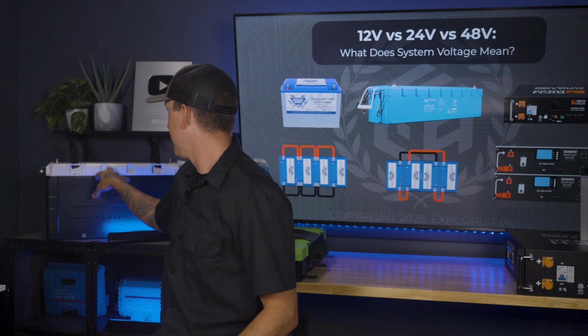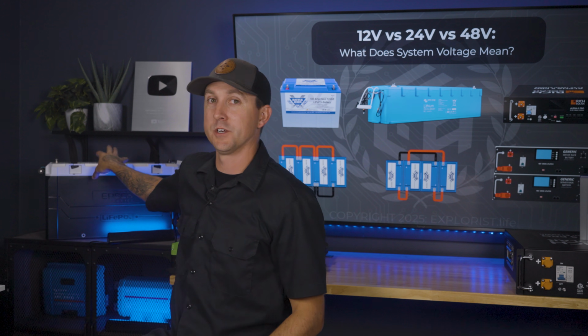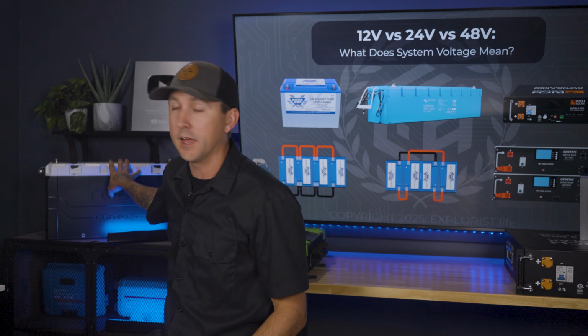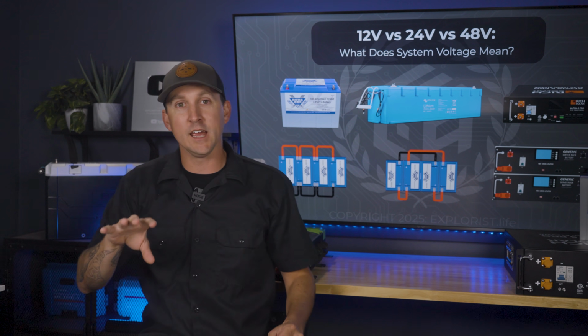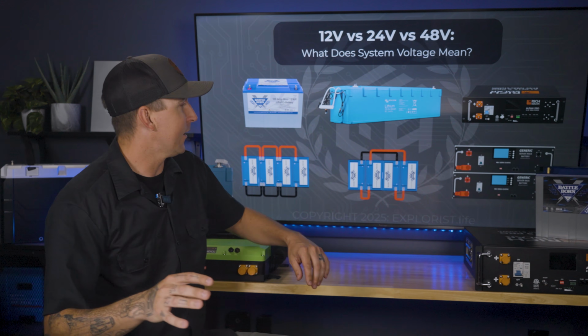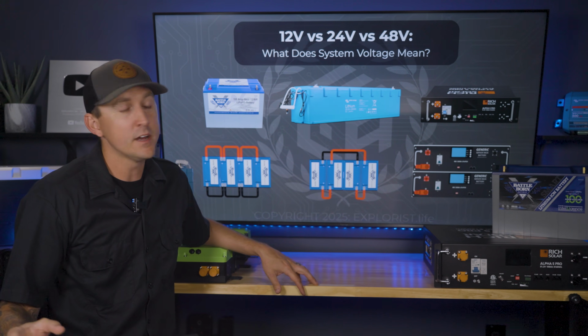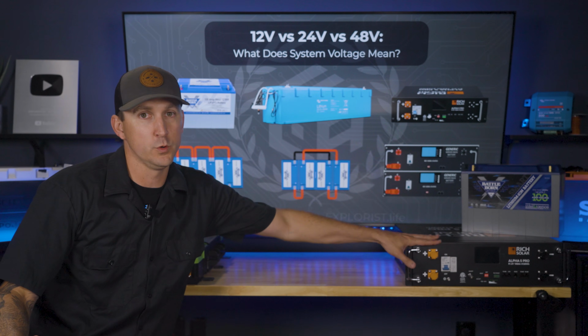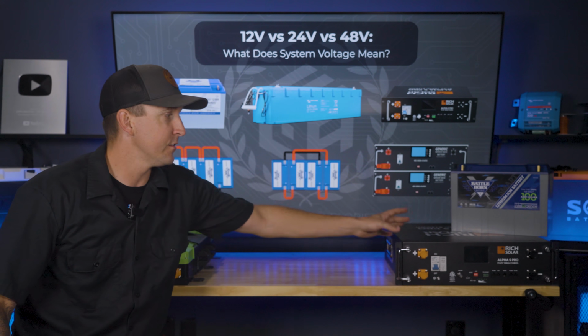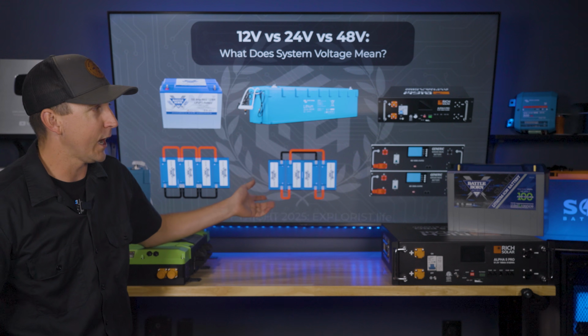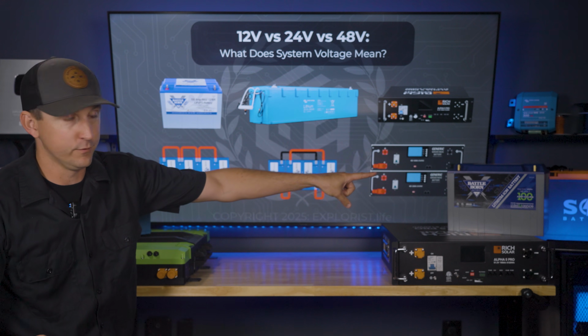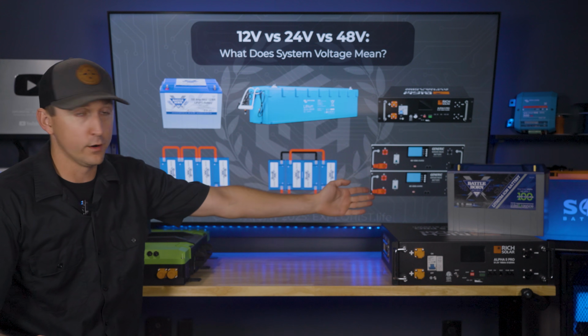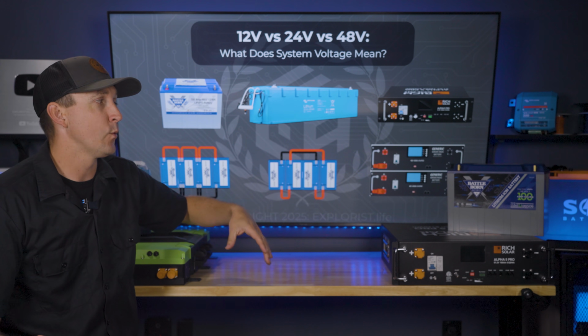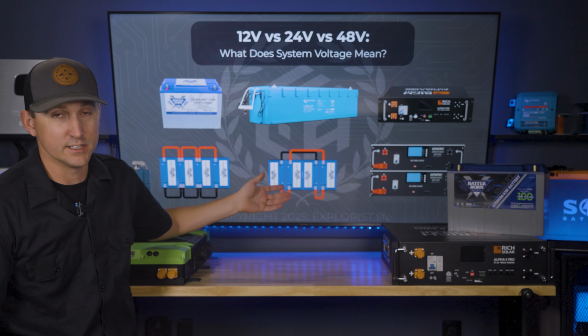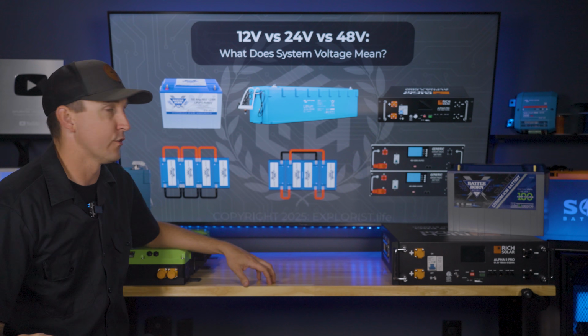Now this exact same battery size and footprint comes in a 12 volt, 24 volt, and 48 volt version. But understand that whenever I'm talking about battery system voltages, I'm not talking about the actual individual battery voltage, because you could have a 48 volt battery bank made up of 12 volt batteries. You would just wire 4 of those batteries in series, like we've covered in previous lessons in this academy, to change the overall system voltage.